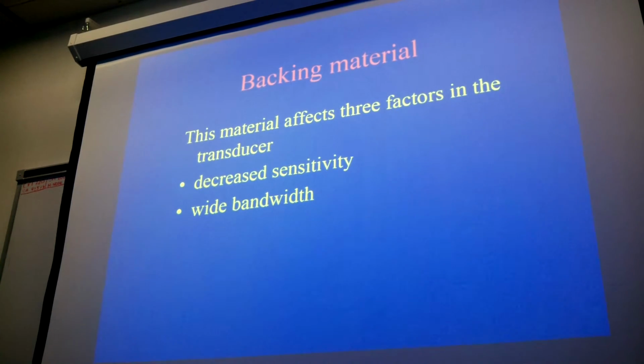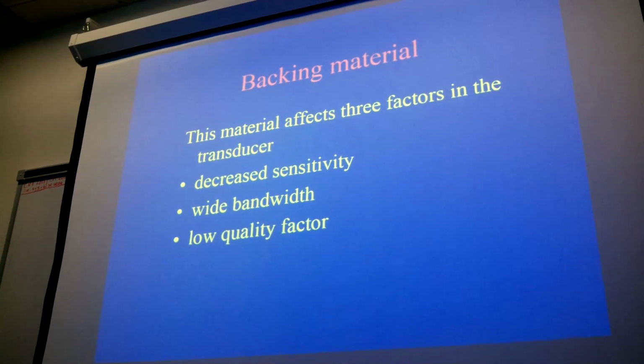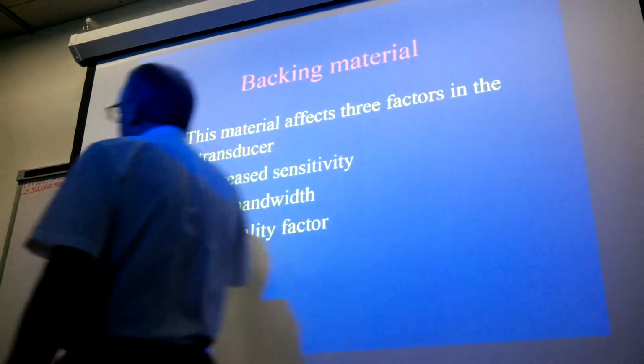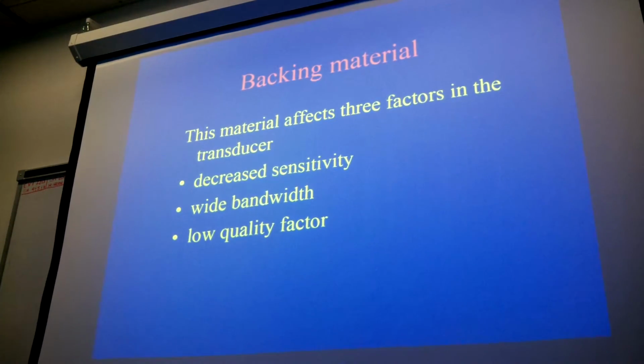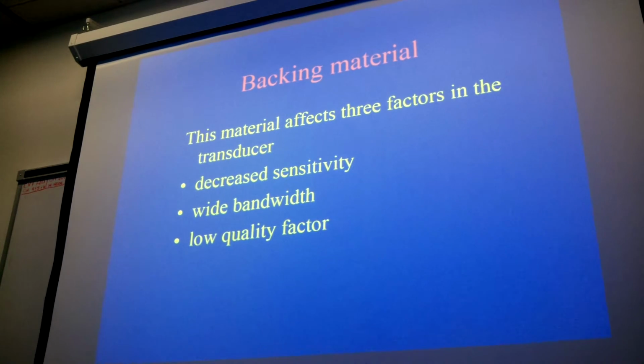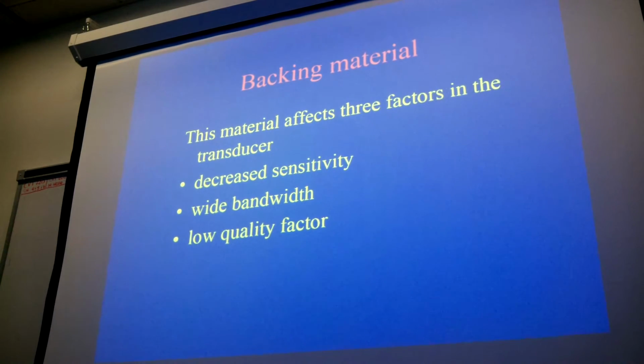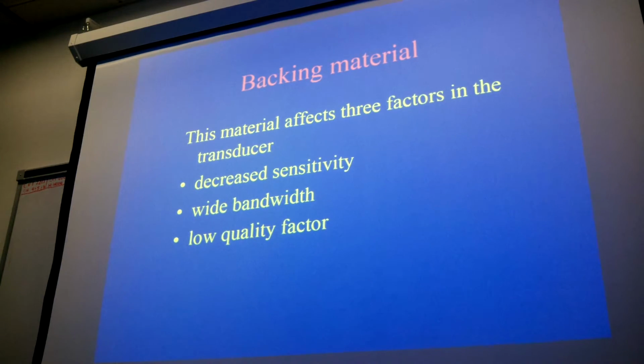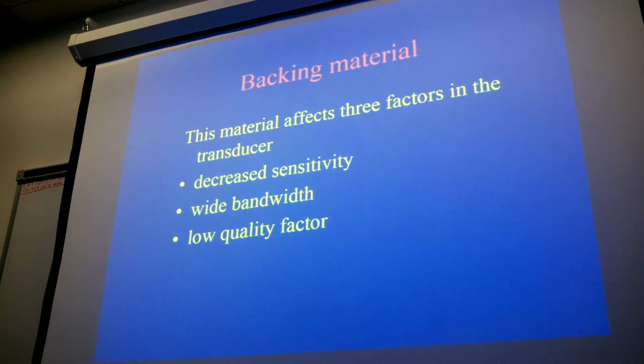It's almost entirely the same transmitted frequency as the electrical pulse you're sending to it. So if I have a 5 megahertz transducer, continuous wave, I'm sending the electrical pulses to it at 5 megahertz. So it transmits at what it receives. Here's the last thing, low quality factor. Low quality factor is just a percentage, and we're going to get into each one of these things. You have a high quality factor for the continuous wave, but a low quality factor for the pulse wave.